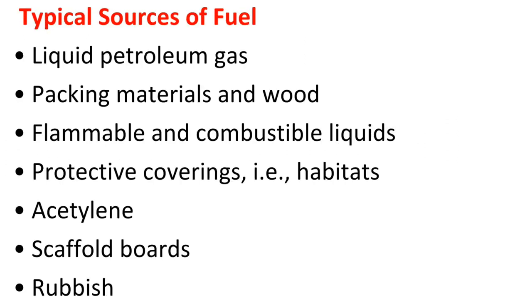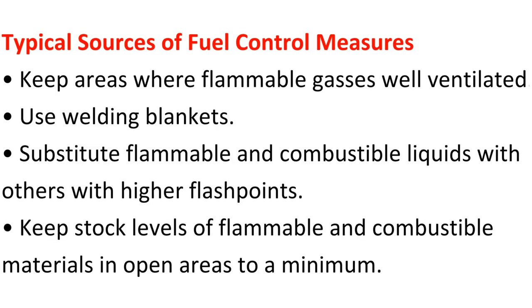Typical sources of fuel include: liquid petroleum gas; packing materials and wood; flammable and combustible liquids; protective coverings, that is, habitats; acetylene; scaffold boards; and rubbish. Typical fuel control measures include: keep areas where flammable gas is well ventilated; use welding blankets; substitute flammable and combustible liquids with others with higher flash points; and keep stock levels of flammable and combustible materials in open areas to a minimum.